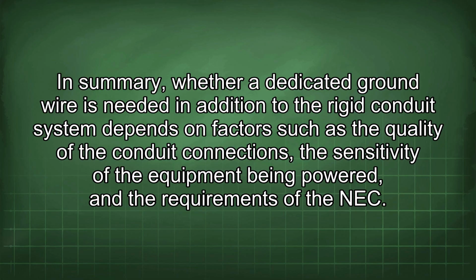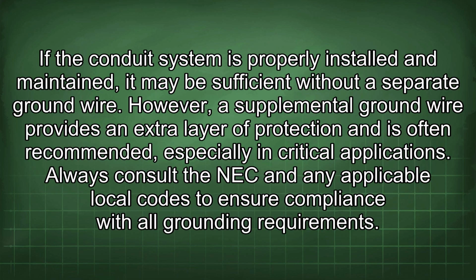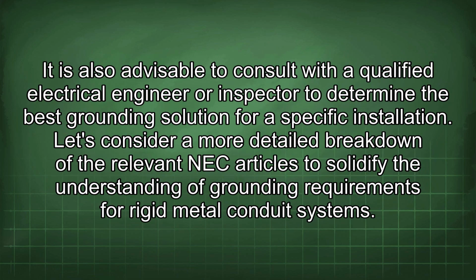In summary, whether a dedicated ground wire is needed in addition to the rigid conduit system depends on factors such as the quality of the conduit connections, the sensitivity of the equipment being powered, and the requirements of the NEC. If the conduit system is properly installed and maintained, it may be sufficient without a separate ground wire. However, a supplemental ground wire provides an extra layer of protection and is often recommended, especially in critical applications. Always consult the NEC and any applicable local codes to ensure compliance with all grounding requirements. It is also advisable to consult with a qualified electrical engineer or inspector to determine the best grounding solution for a specific installation.